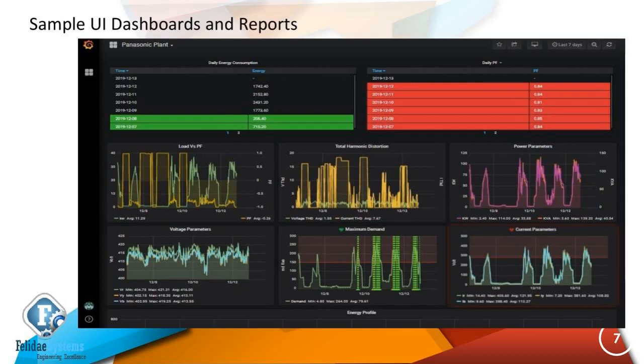As I said about power and flow, from the analysis point of view, we should know this aggregated, cumulative value. For example, if our process is designed for consumption of say 1,000 liters of water per day, and on a certain day the consumption was 1,100 liters, then we have to look into the instantaneous flow parameter. This lets us pinpoint the time when the flow of water was more, and figure out the reason.